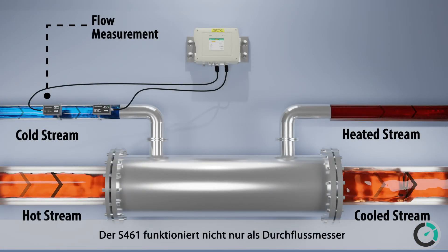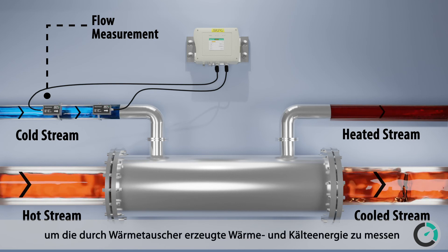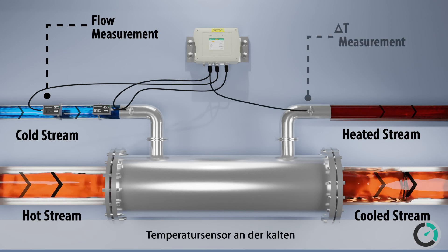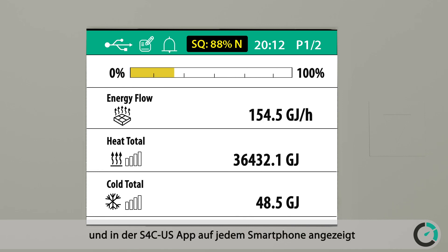The S461 not only works as a flow meter but can also be used as an energy meter to measure the heat and cold energy generated through heat exchangers. Users can easily connect additional temperature sensors at the cold and hot sides of the heat exchanger. The heat flow and thermal energy are calculated automatically and displayed on the screen in the S4C-US app on any smartphone.